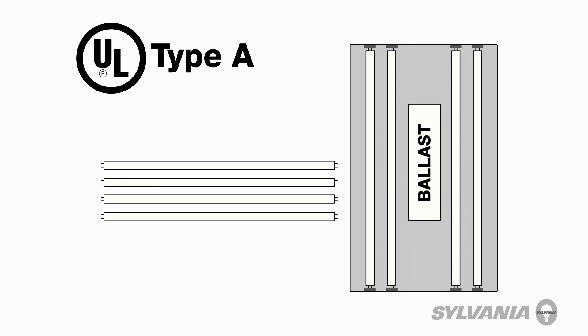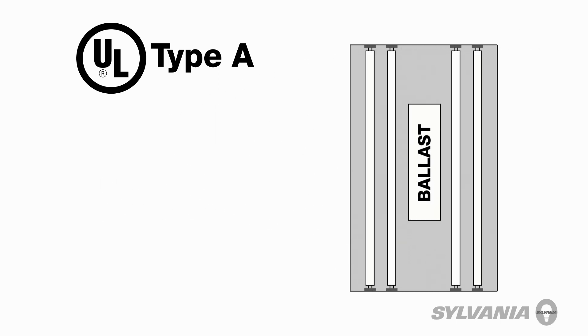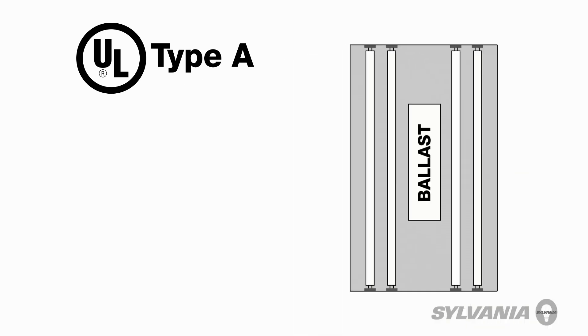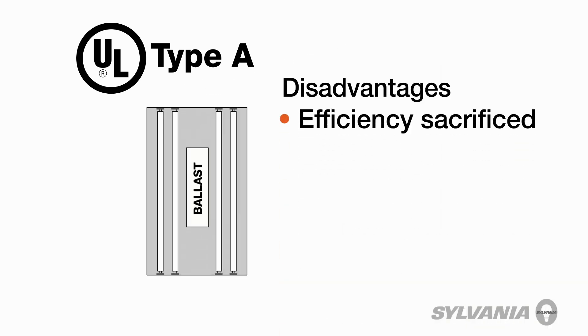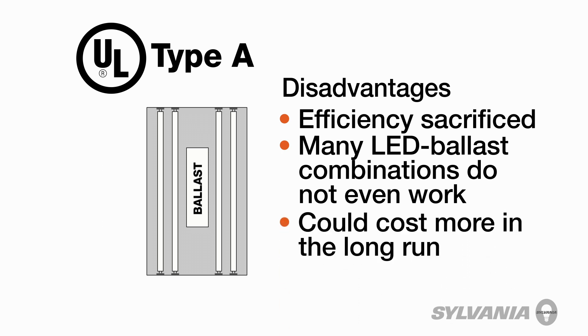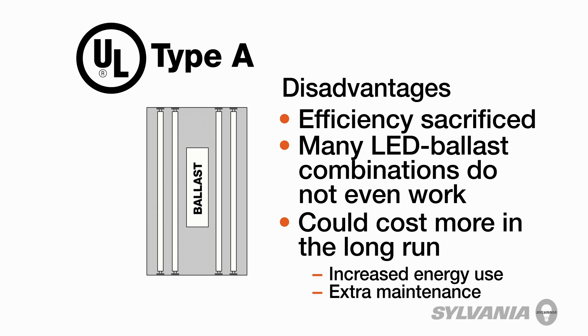UL Type-A LED lamps offer a quick and easy replacement by using the fixture's existing ballast. Retrofitting involves swapping the existing fluorescent lamps with the appropriate LED lamps, such as Sylvania SubstiTUBE lamps. However, there are trade-offs to this installation's simplicity. Efficiency is sacrificed due to power loss using the ballast, and there are many LED ballast combinations that do not even work. While this approach offers a low initial cost, it could potentially cost more in the long run due to increased energy use and extra maintenance required when existing ballasts need to be replaced.